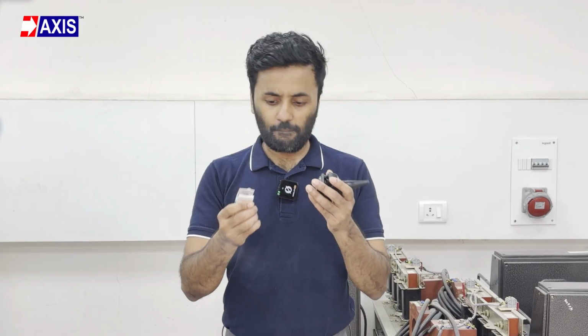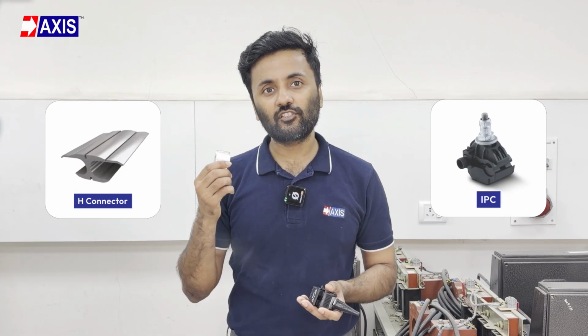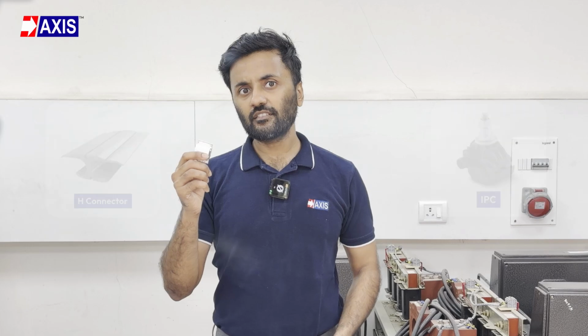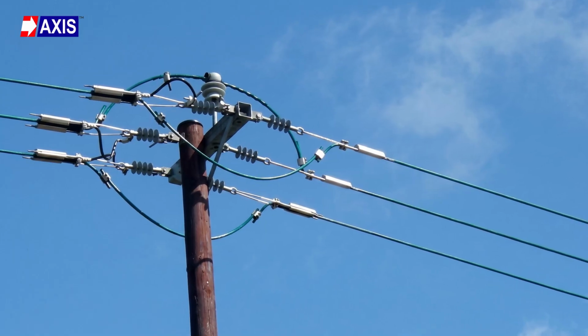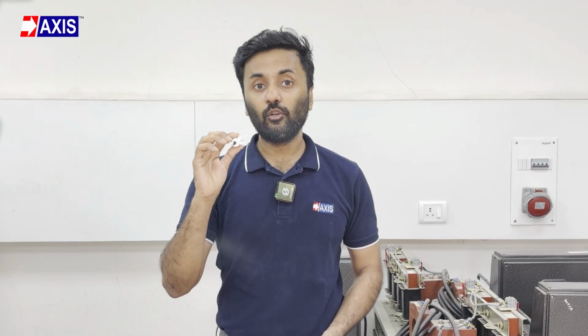But before we compare these, let's understand what they actually do. H connectors are used to join bare or insulated conductors permanently. You strip the insulation, insert the conductors into the H-shaped connector, and then compress it using a hydraulic crimp tool. This creates a permanent, low-resistance joint that handles high current and mechanical loads in overhead distribution lines.